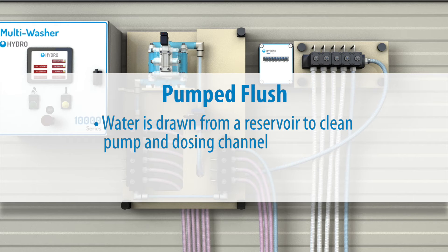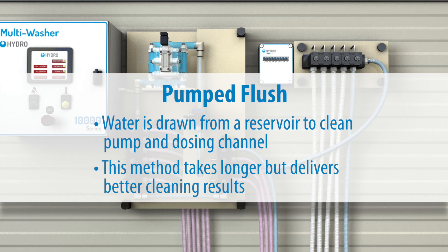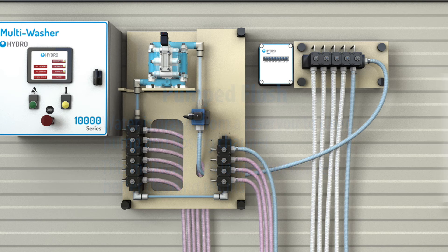Alternatively, with a pumped flush, the pump draws water from the reservoir much like a product to clean the pump and dosing channel. This method takes longer but typically results in better cleaning of the pump and channel. Regardless of the method chosen, when the water flush is completed, the collector valve and distributor valves are closed and the channel dosing process is ready to begin again.